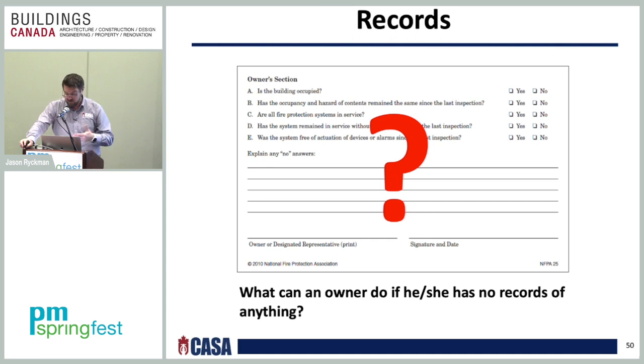Especially if it's a hydraulically designed system, then the requirement for a riser tag is provided in section 526. So if you're missing that, how are you supposed to know? The owner is required to provide that information. Remember that we are operating under the assumption that the system was installed and accepted as correct. It is the owner's responsibility to verify compliance with NFPA 25. The standard does not address the situation where a hydraulic tag is required. Common sense would tell us that it is not required if the system was not hydraulically designed. However, we are simply to verify the presence of the tag. It is the owner's responsibility to provide that information.